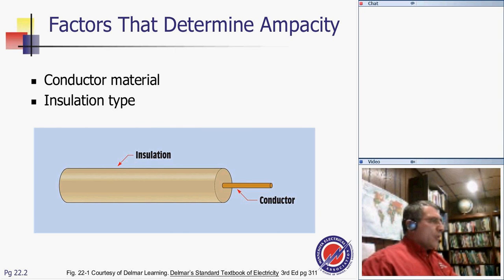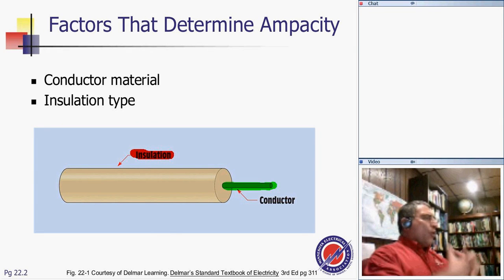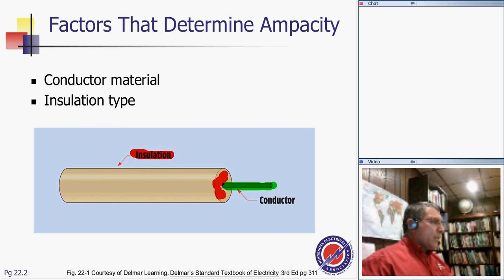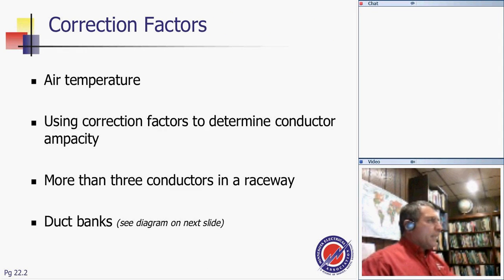About conductors, guys, the single most important thing is the conductive material, copper or aluminum. That's how we carry the current. The second most important thing is the insulation, because here's a catch-22, guys: the better the insulation, the worse the heat. Insulate it more, then the heat will sit more inside. It wouldn't be dissipated, and of course, it will deteriorate the insulation. So that's the catch-22. You need insulation to insulate the voltage, but at the same time, you are wrapping the conductor with something that the heat cannot dissipate through.